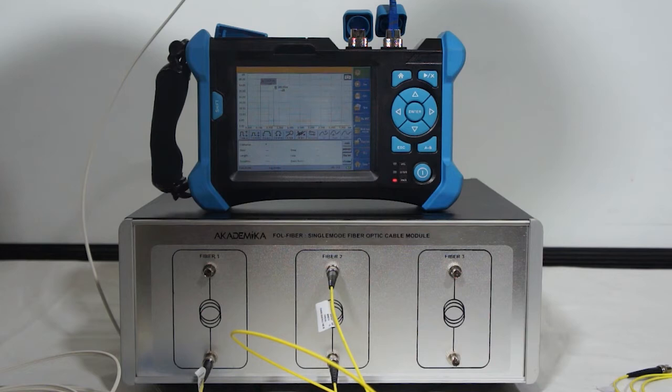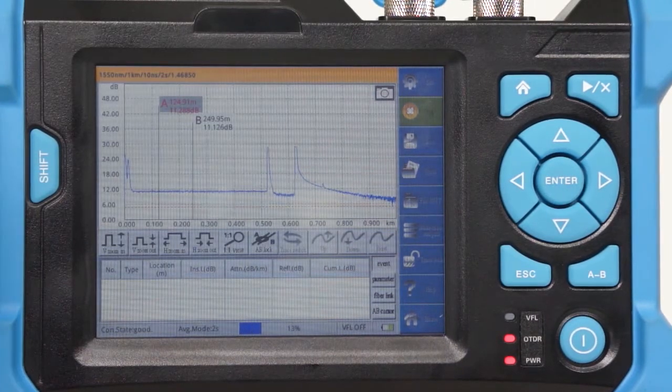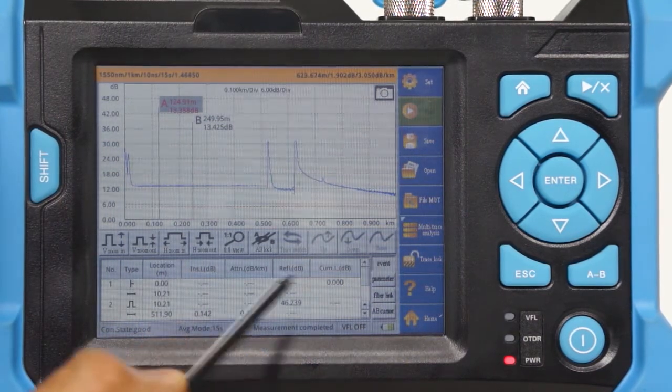As discussed earlier, the OTDR parameters like the wavelength, range, pulse width, average time, and IOR are set as shown. Then we run the OTDR and see the OTDR trace. The OTDR displays the power of the reflected signal related to distance. The OTDR measures the position of events, attenuation coefficient of fiber, and loss of a single event. The analysis of the trace can now be done from the Event tab.